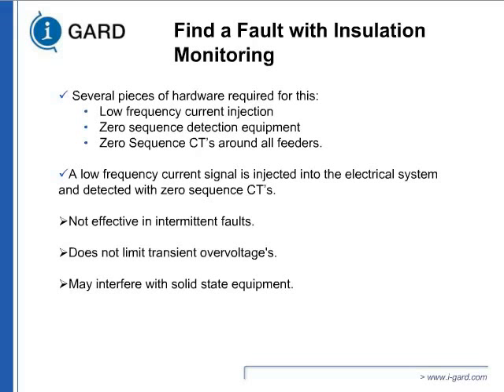The reason for that is, a power system doesn't depend on the ground current. Solid state equipment does. When you inject this current, it ends up in the ground wire, and it may trip your solid state equipment. So we essentially took all the insulation monitoring online off the circuit. You cannot shut the process down. If the main goal was process continuity, you cannot introduce a product that will reduce that probability.